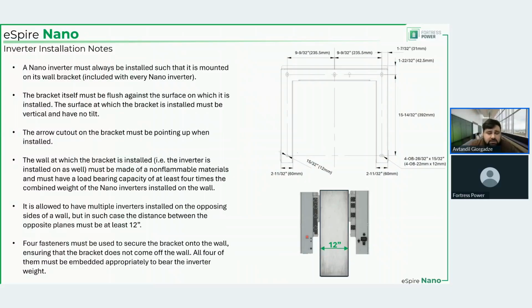There are 4 screws that go into each corner of these brackets, so all 4 of them must be used. It's not like you can put the top 2 and skip the bottom 2. That will not have the system structurally balanced. It is allowed to have one wall supporting 2 inverters on opposite sides. But in that case, the width of the wall, i.e. the distance between the brackets, must be at least 12 inches. And the wall, whichever one you use, must be able to bear 4 times the total weight of all inverters that the wall is to support.